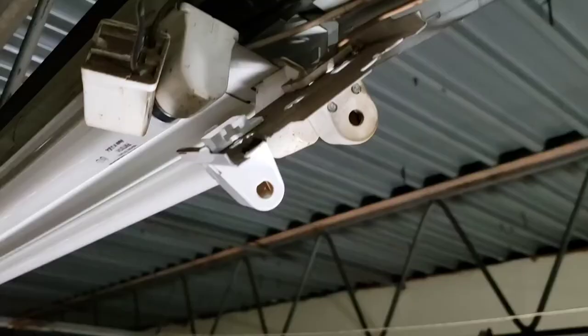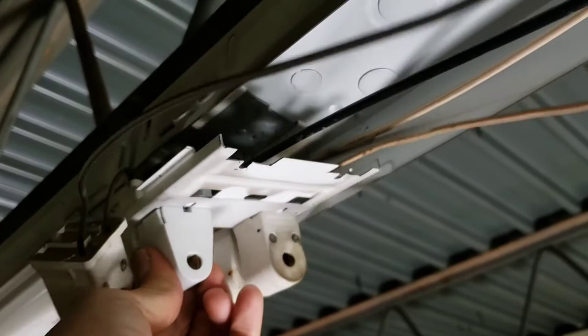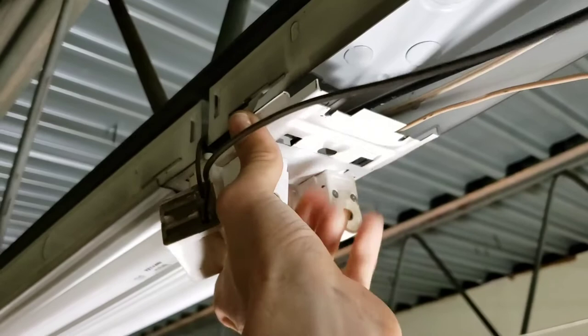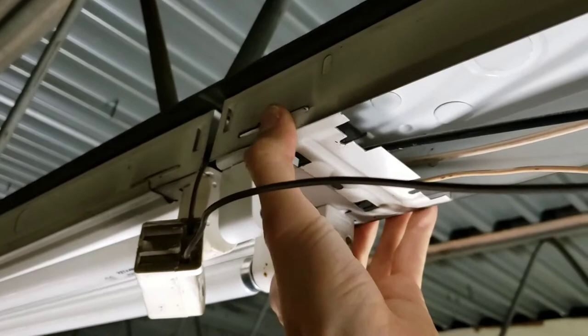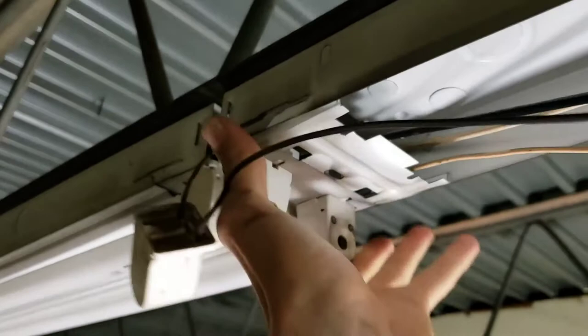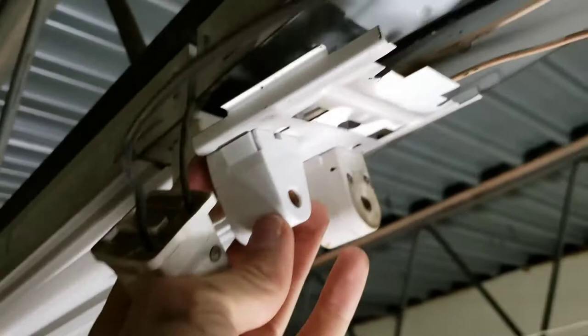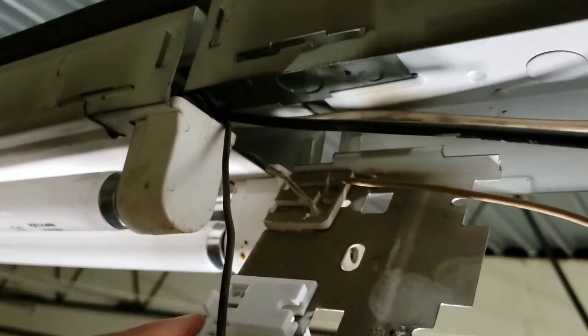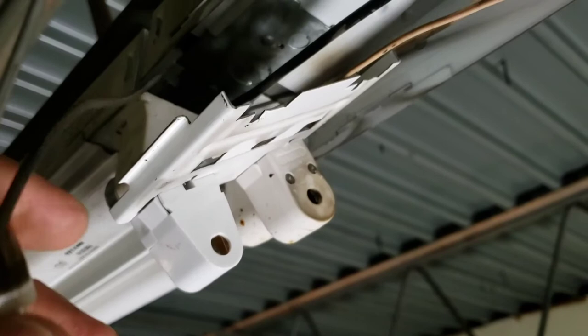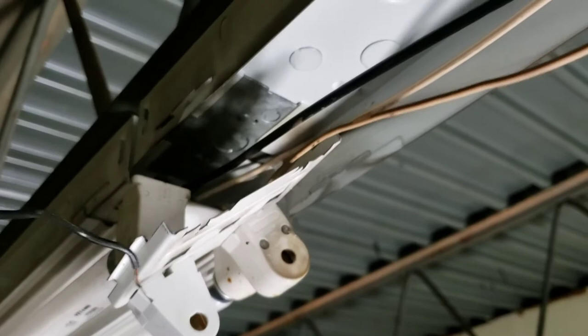At this end of the light fixture, this just snaps in and out like that. This is the old connector here and I slid in the new one. The new one slides in just fine even though it has a quite different shape to it. It's a different brand, not the Leviton brand, but this was easier. This wire is loose, which means that something is loose in there and that might explain the bad connection. It's hard to tell if this is burned out in here but the contact is not great, so we're going to go ahead and replace it.